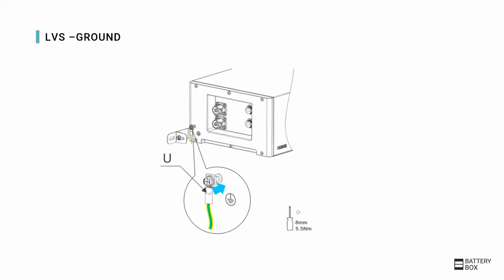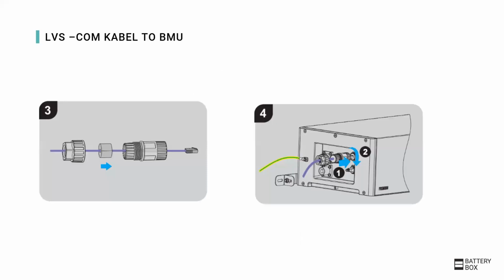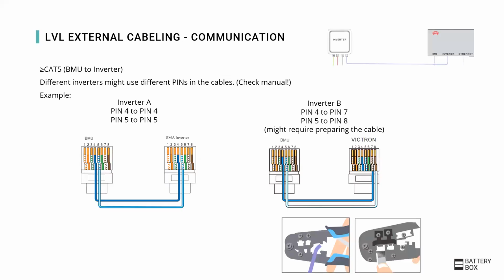First, the ground cable, which should be directly connected to the earth of the house, then the communication cable to the BMU. As the LVS fulfills IP55, a special connection cover is used to protect the communication cable. The communication cable connecting from the BMU to the inverter is exactly the same as for the LVL and the LVS. Again, dependent on the inverter, this might require special communication cables.